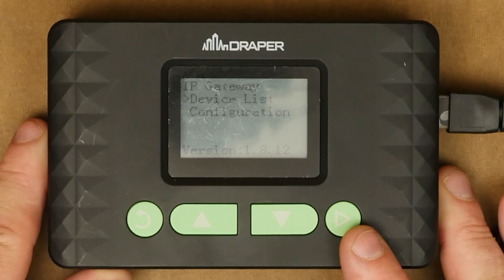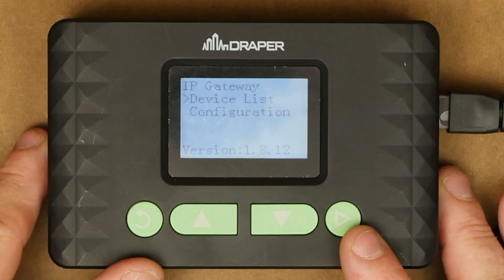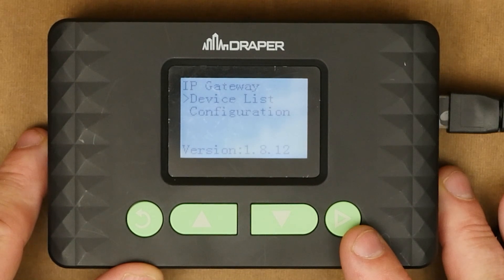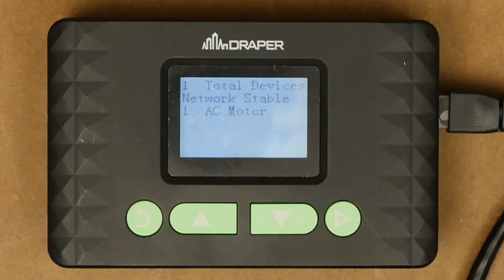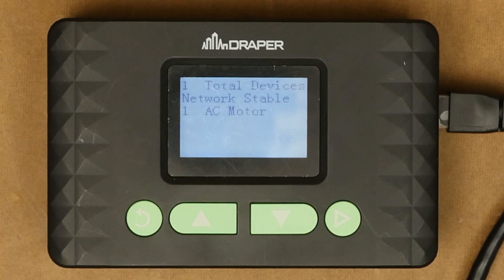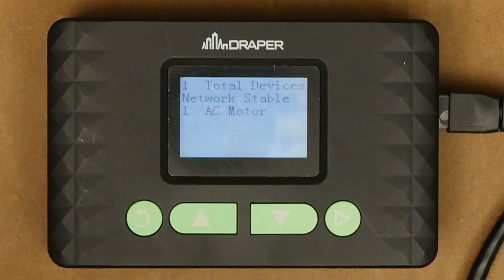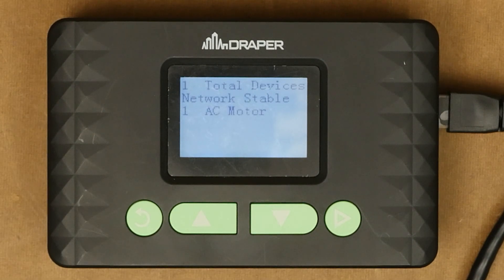On the main menu you have two options: device list and configuration. I'm going to jump into device list first. This is a good tool for troubleshooting when you walk on site. You select device list and it's going to give you a breakdown of everything currently tied into the network. As you can see I only have one motor currently plugged in so it reads as one total device. My network is stable and my one device is an AC motor. If you have 15 motors and three switches connected it's going to populate and say 18 total devices and give you a breakdown of how many motors and how many switches you have.